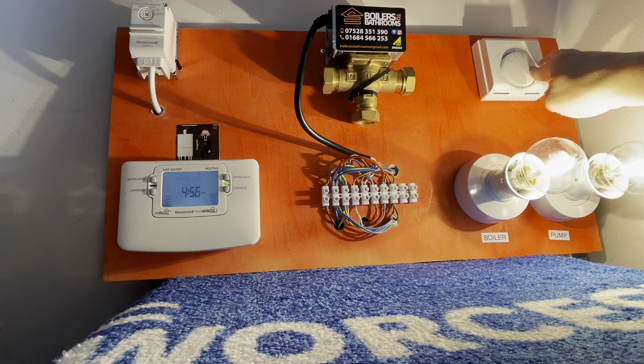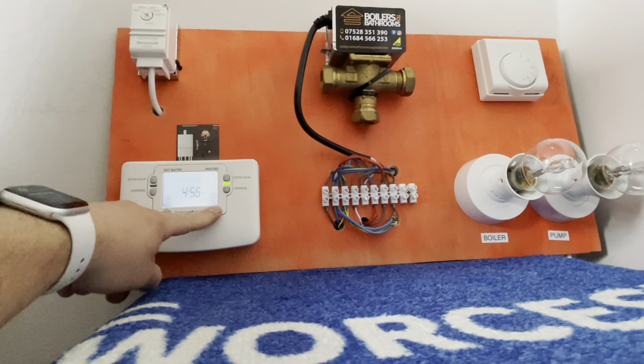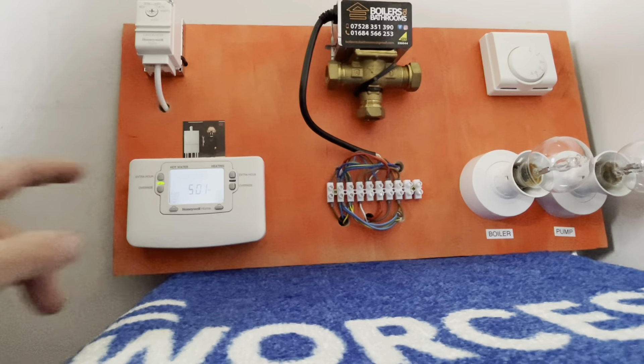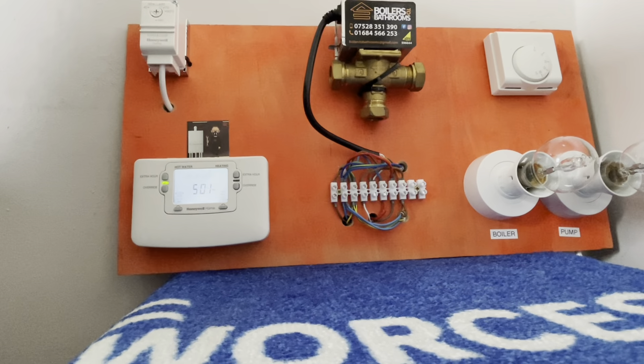I'll go through the wiring diagram during that. So we'll turn heating off, and now I'll demonstrate with the hot water — turn to constant. The cylinder stat was calling — you can hear the zone valve spring back, and obviously the boiler and pump fire. If we turn it to off, it goes off again. So I'll go through the individual components in a bit more depth one at a time.